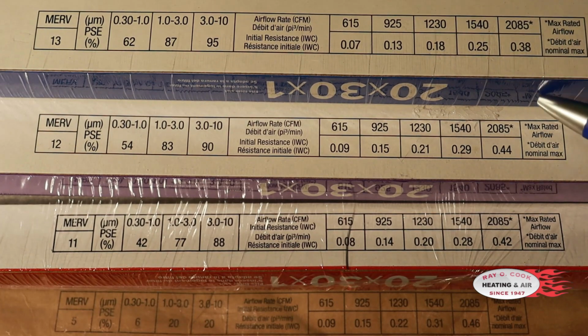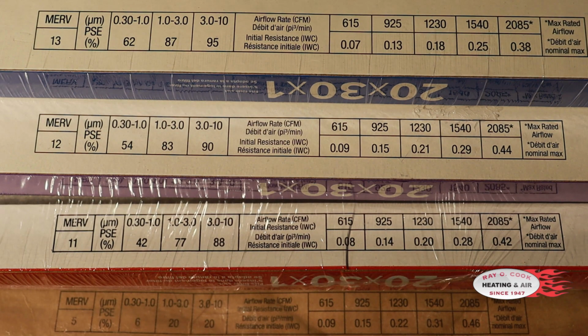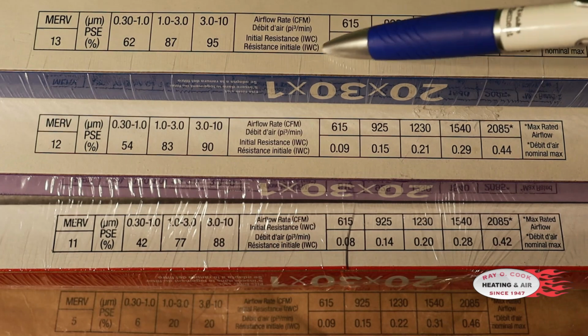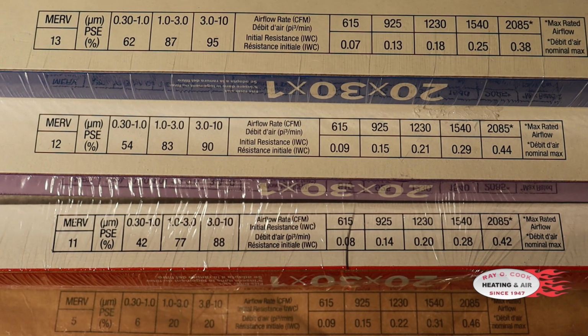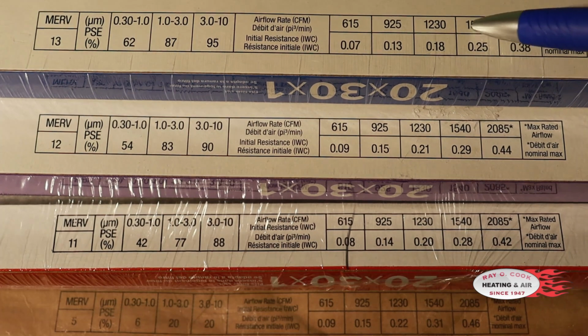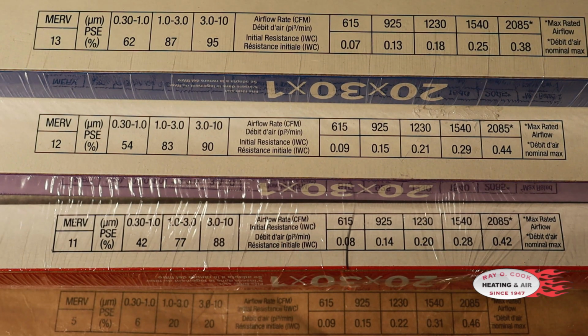So again, we only have 1 inch thick capability here to be able to catch all of these particles that the filter will catch. It does have the ratings, but once it catches them, what is it doing to the resistance of your airflow and your fan motor and your lack of airflow when it starts to load and when the AC unit is not delivering the tons of air that you're paying for because we're restricting the airflow so high.